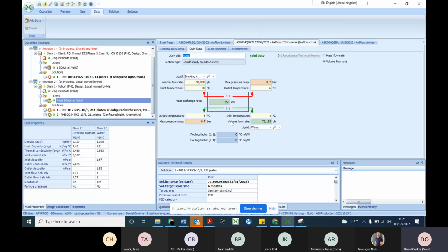I have to disagree with what you're saying. Sorry. Okay, but this is a learning curve. First of all, the temperature of the outlet can be higher. If you lower your flow rate, you see here, actually you need 72 cubic meters of ice water in order to get an outlet of 5. Meaning the customer would have to purchase a huge pump, right?